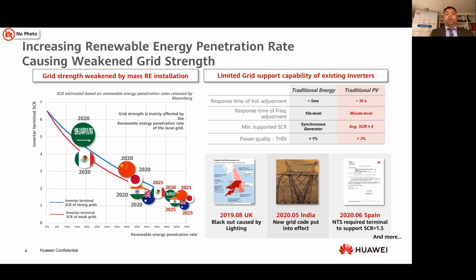We have been thinking of PV inverters as basically injecting current to the grid, anchoring on the grid voltage. But now, thinking more as grid forming, the system is able to provide its own voltage capabilities, provide a lot of ancillary services, participate in black start when needed with renewables, effectively work as a harmonic sink, work in very weak grid situations, do microgrid islanding and grid tied operation, and provide better responses for the power systems.